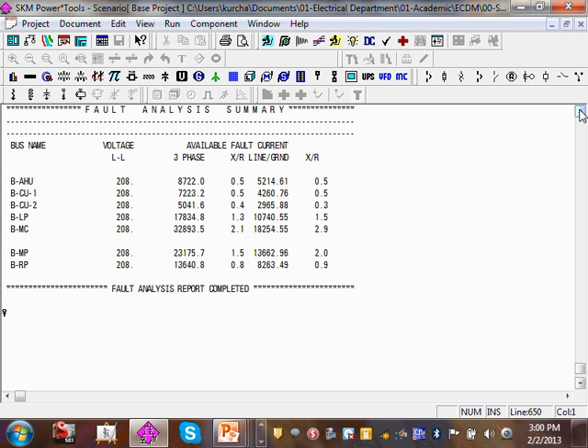Now, at my main panel, if my available short circuit is 23, and I installed 10,000 amp interrupting rating circuit breakers, what you saw in the video, when the circuit breaker exploded, that's exactly what's going to happen.